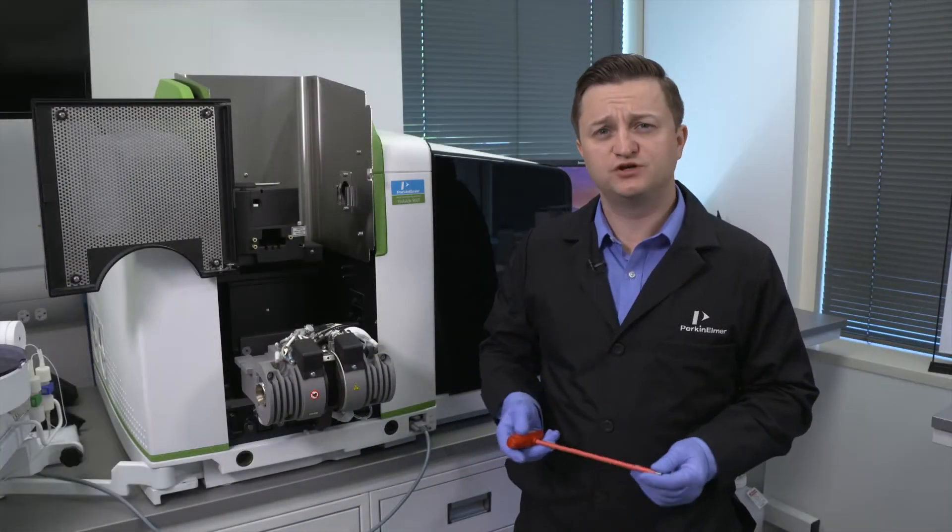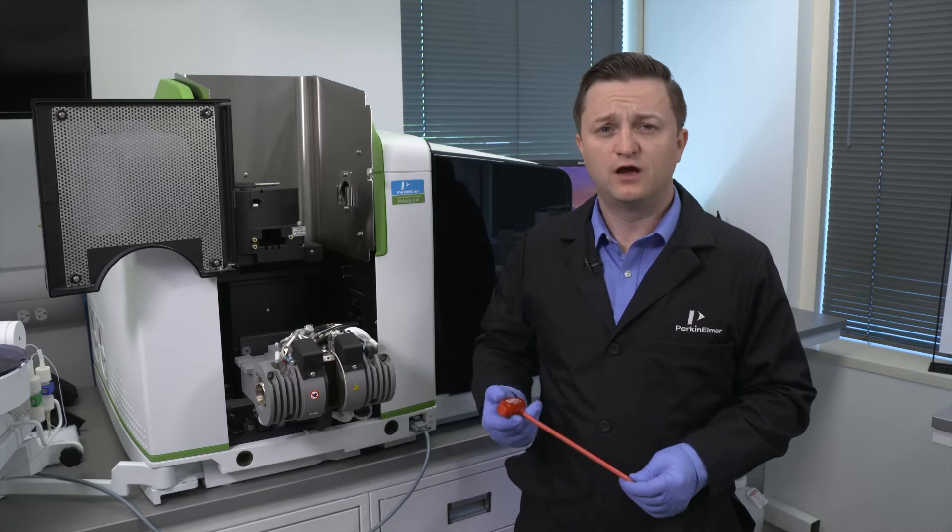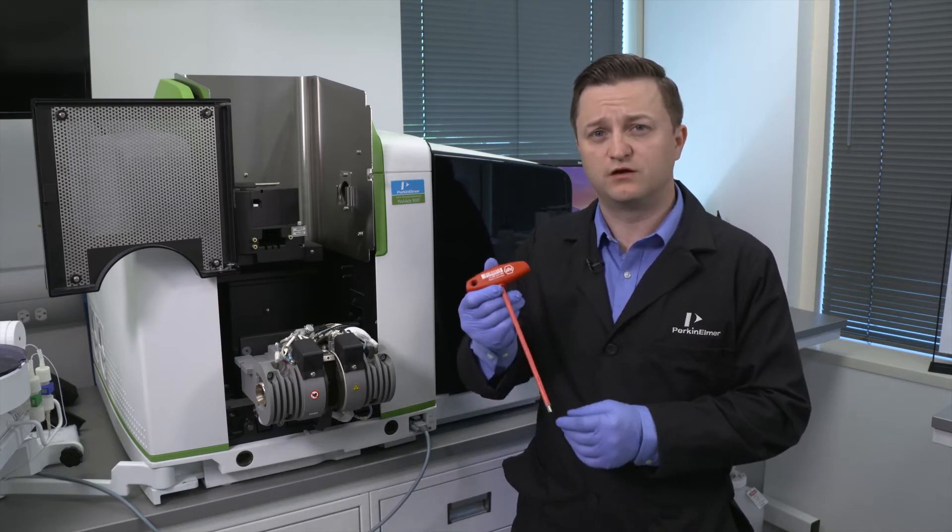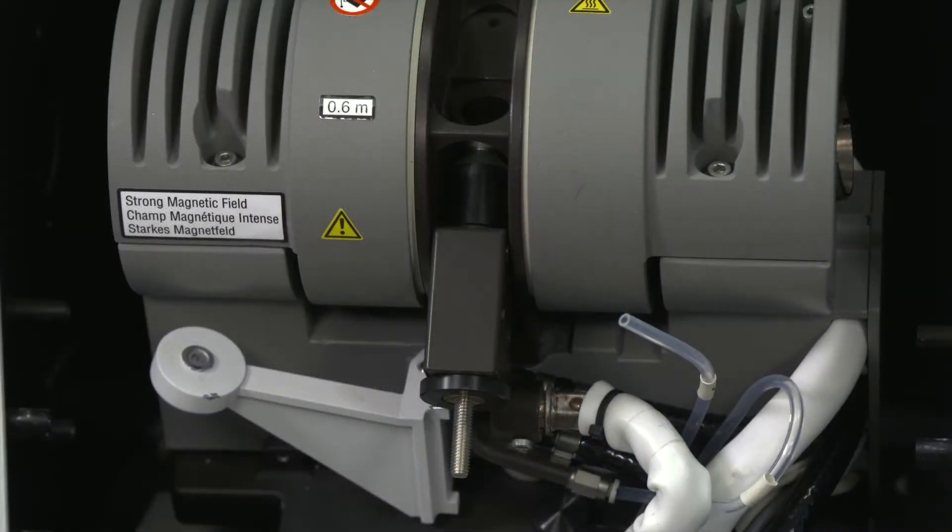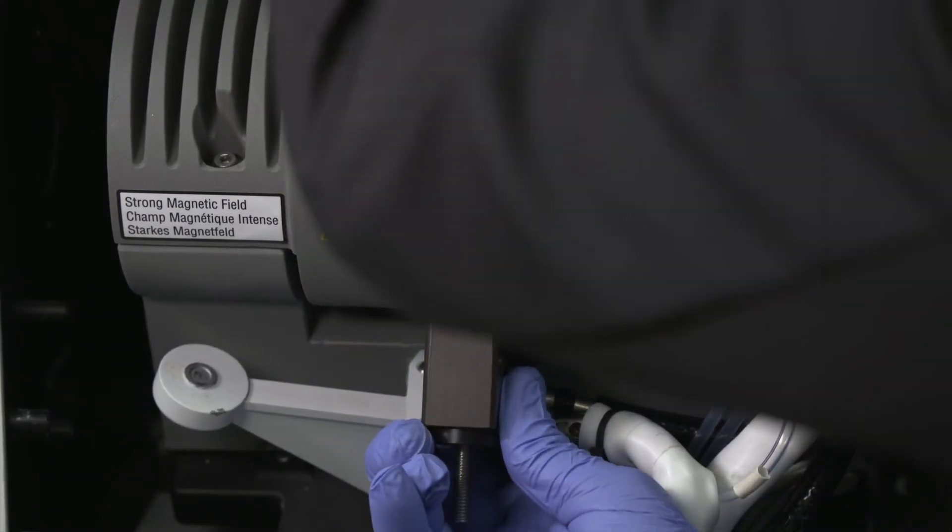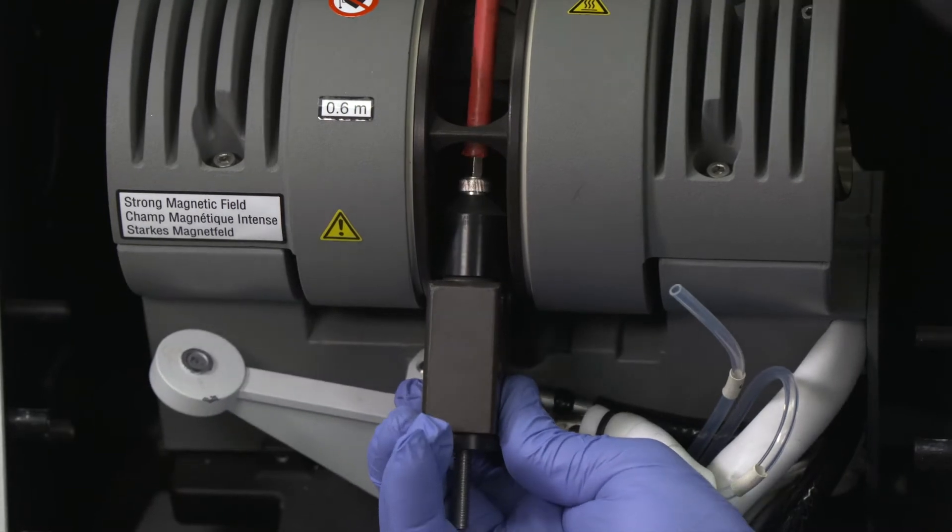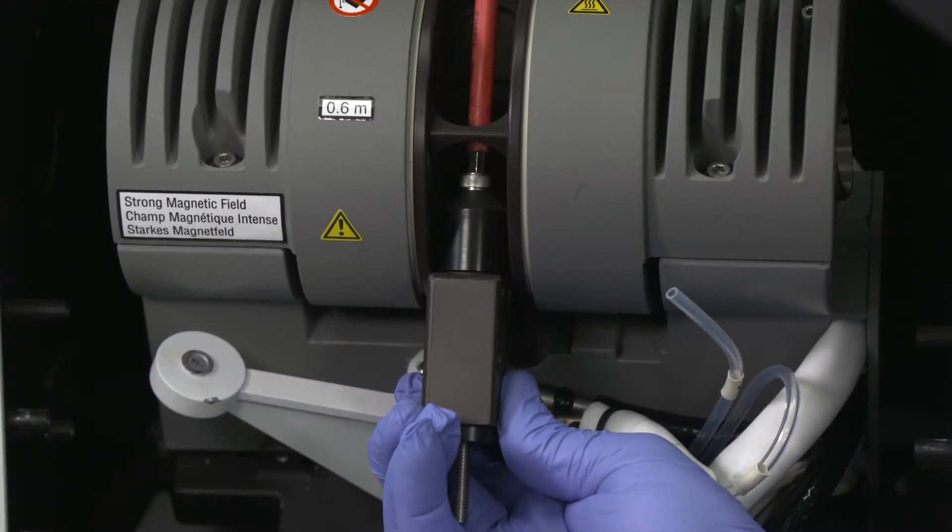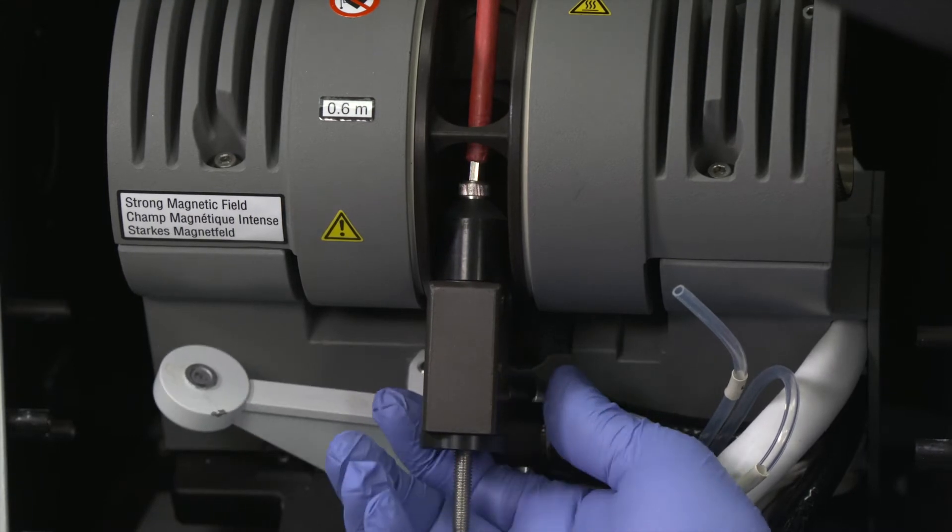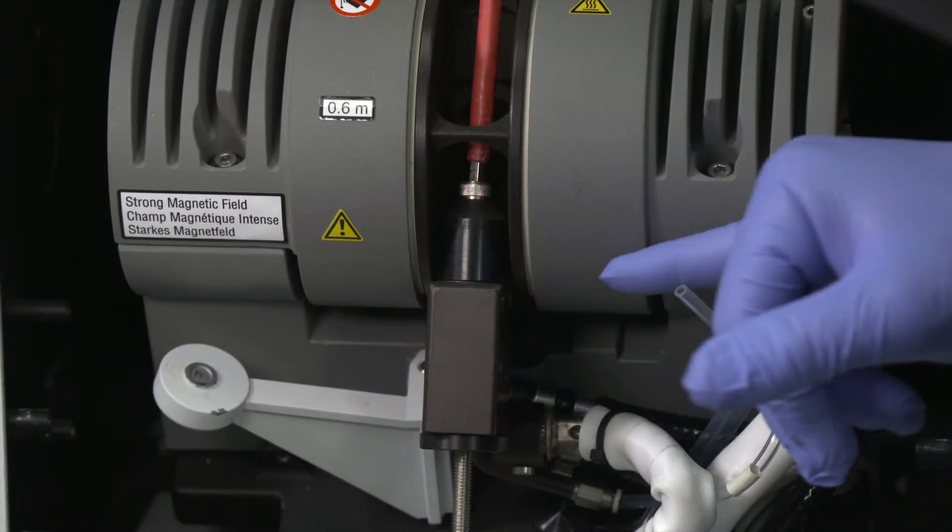Now to push in the front contact cylinder, I recommend the use of a long hex driver. Tilt the furnace back into its original position. Use the hex driver to screw the bolt into the threaded cylinder and push the contact into the contact housing. Now screw in the bolt until the rim of the contact is flush with the contact housing.